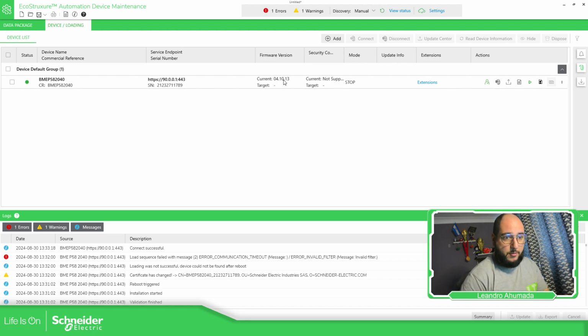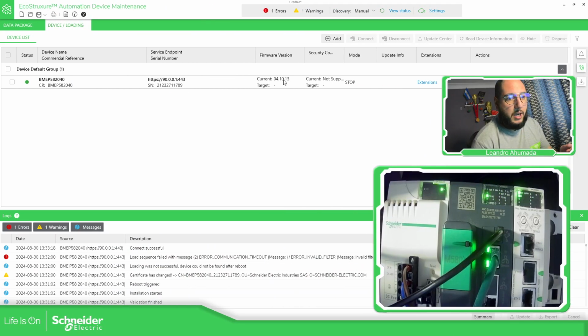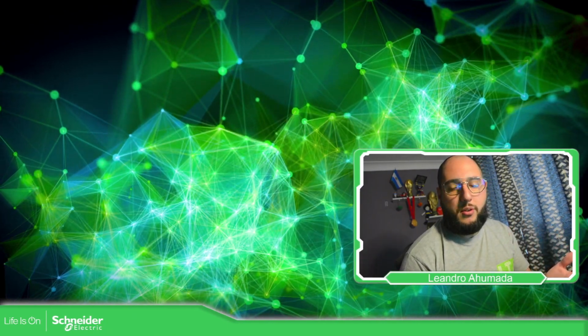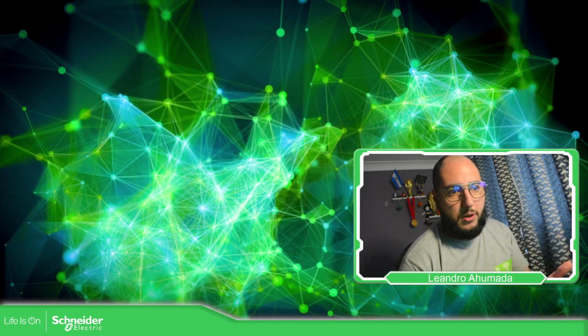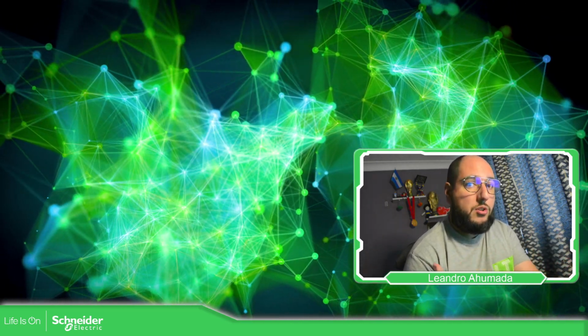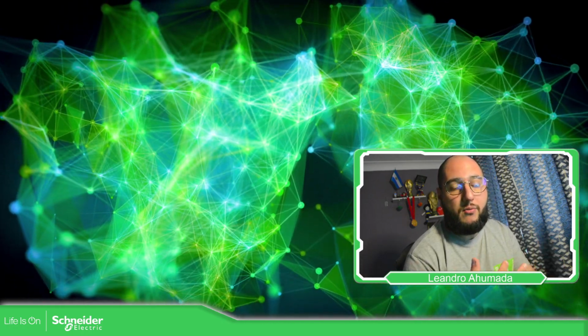I already selected. Okay, so this is how you can make the upgrade of the old M580 version 3.20 in my case, to the intermediate version 3.99, and then to the last version that I have already selected, which is the 4.10, but there are other ones, so we can create a different video for that. But this is the whole process, how to make the migration of the firmware from the older one to the new one using the EADM, EcoStruxure Automation Device Maintenance, and using the firmware package for the update.